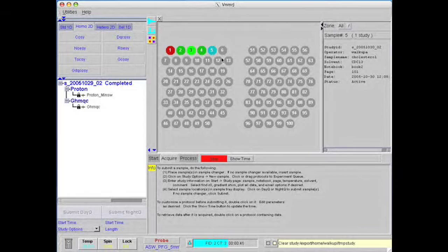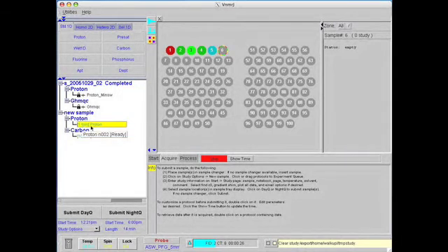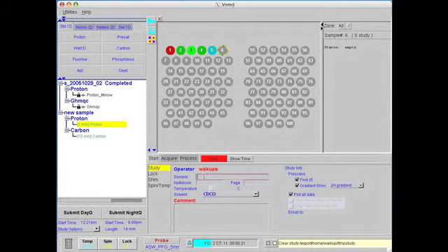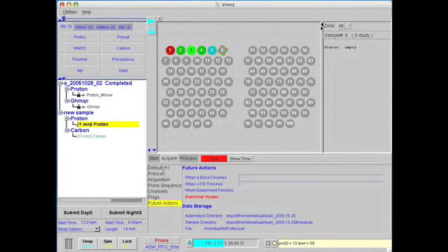First, click on location 6, select a proton and a carbon experiment. Enter the sample, book number, page number, and a comment. Check the solvent. To customize the parameters for the proton experiment, double-click on the time field. Wait until the progress bar is done. The Acquire tab will now show customizable parameters. Choose the number of scans.